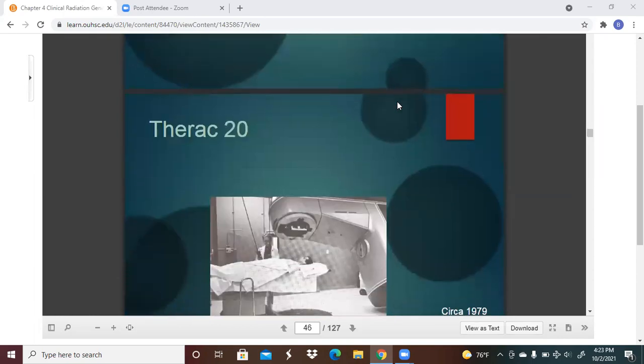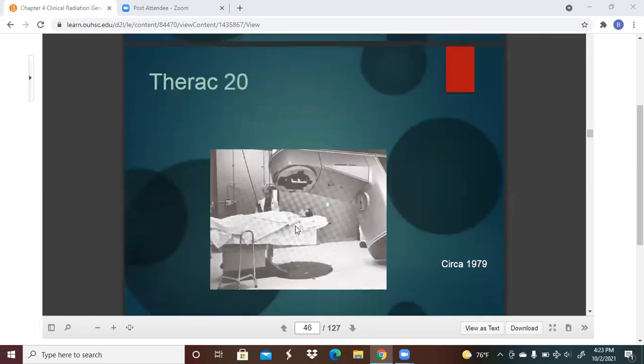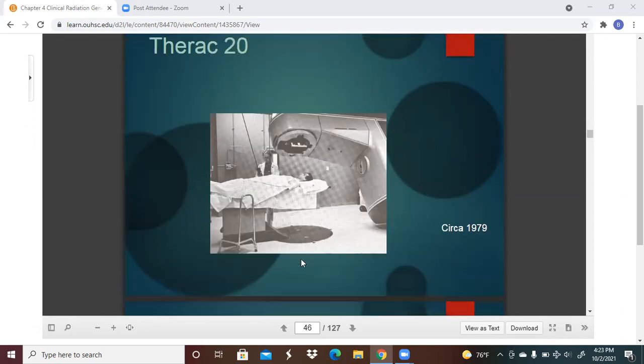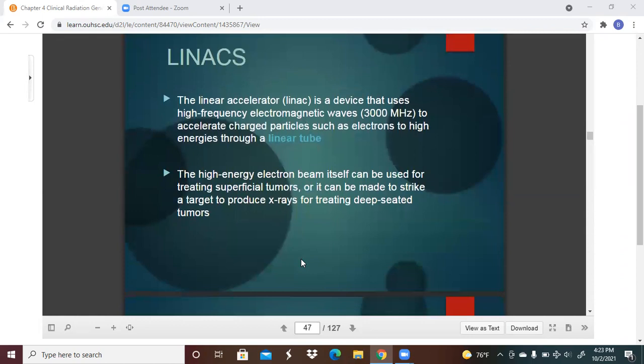by the linear accelerator, which is what we've all come to expect when we walk into our therapy rooms nowadays. Not so much a Therac 20, but something that looks like those. So the linear accelerator, or Linac for short, is a device that uses high frequency electromagnetic waves, or 3000 megahertz, to accelerate charged particles such as electrons to high energies through a linear tube. The high energy electron beam itself can be used for treating superficial tumors, or it can be made to strike a target to produce X-rays for treating deep-seated tumors.